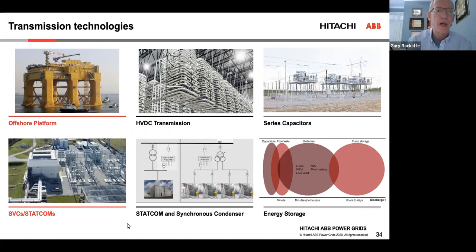The lower left is STATCOMs. STATCOMs help with basically relaxing the transient stability limit of lines. I have another slide that specifically addresses STATCOMs. And then the STATCOM and synchronous condenser is a hybrid solution which combines the capability to support voltage of the STATCOM, and also the capability of a synchronous condenser to inject real power into the grid to support frequency and provide short circuit capability. And then on the far right, lower right corner, storage.